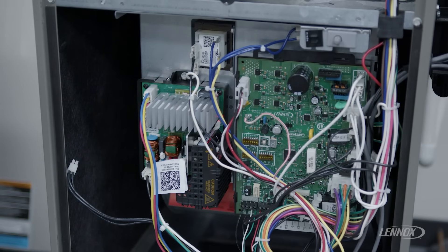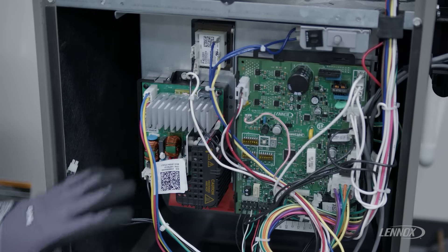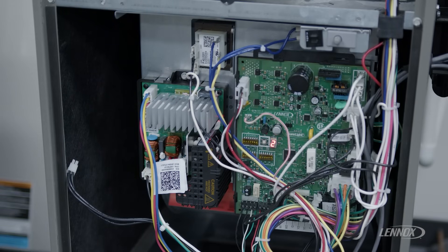Now it's extremely important to make sure that we power this system down first, as there are capacitors on this blower drive board that will remain charged for a short time after de-energization. So as you can see, the lights on our blower drive board stopped blinking, and it is now safe at this point for us to get in here and start some troubleshooting.